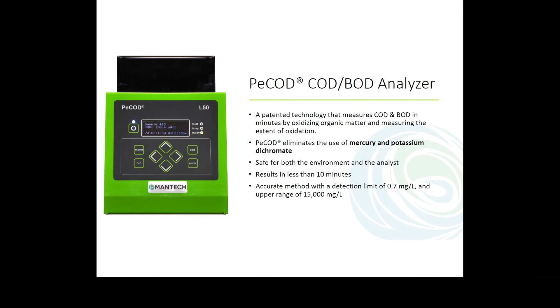Getting to the PeCOD, the COD/BOD analyzer eliminates chromium and mercury entirely—it's gone from your facility. It's safe for both the environment and the analyst, and the detection limit is low, less than 1 ppm, third-party verified and published.